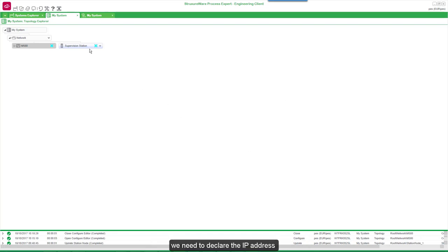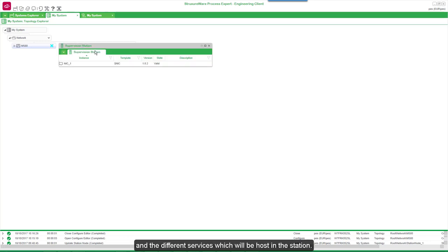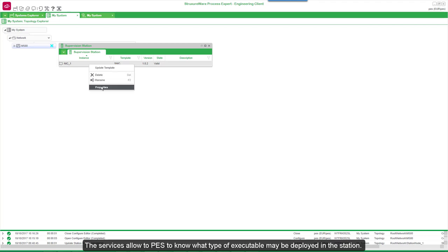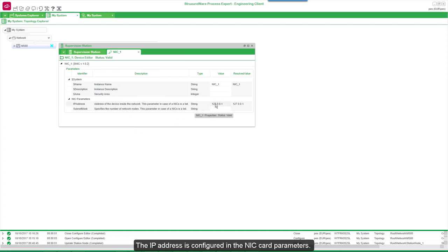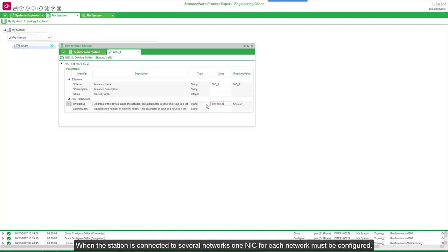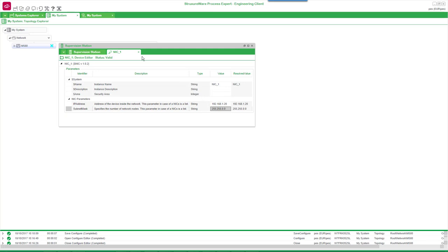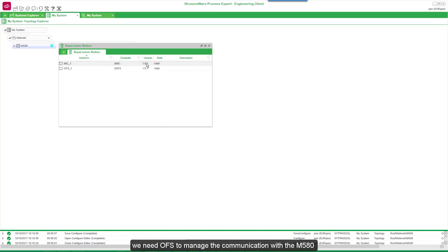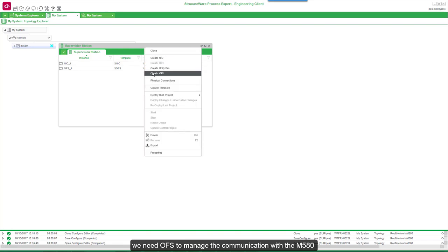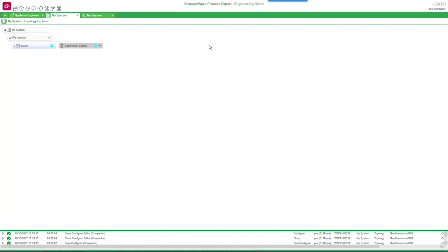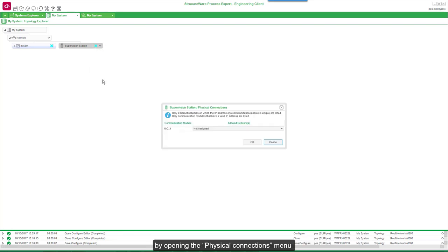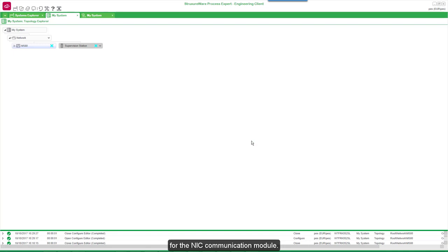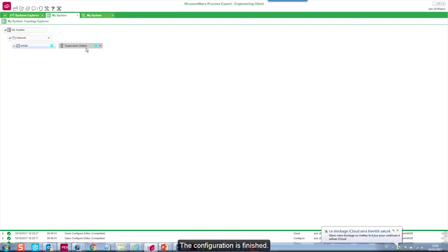For the supervision station, we need to declare the IP address and the different services which will be hosted in the station. The service allows PES to know what type of executable may be deployed in the station. The IP address is configured in the NIC card parameters. When the station is connected to several networks, one NIC for each network must be configured. For the supervision server, we need OFS to manage the communication with the M580, and the supervision service, Vijeo Citect. Now the supervision station must be connected to the control network by opening the Physical Connections menu and selecting Control Network for the NIC communication module. The configuration is finished.